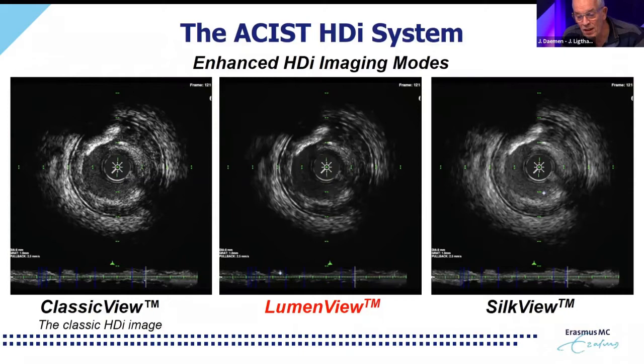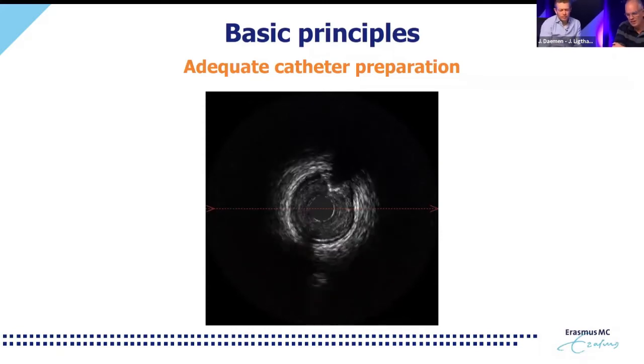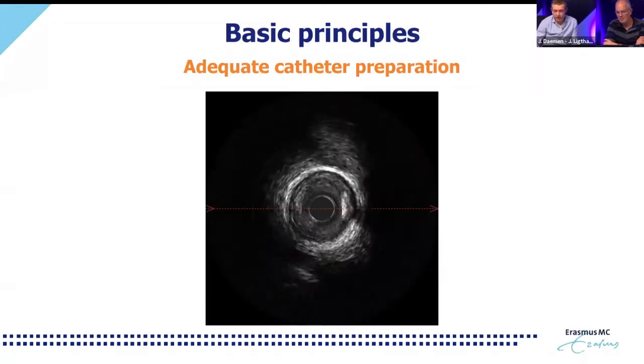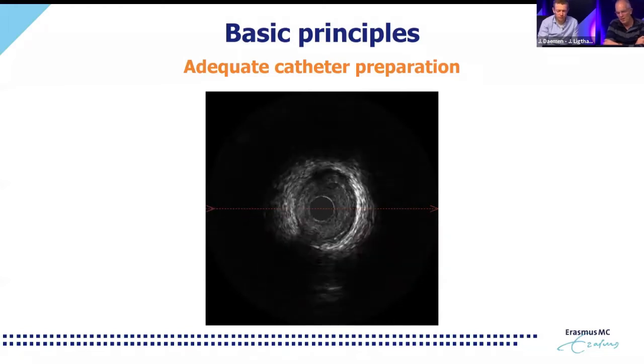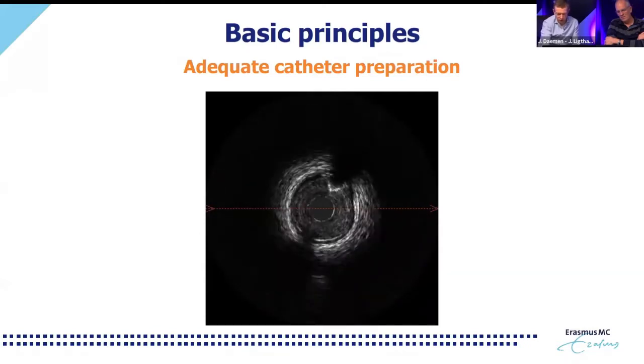Some basic principles when starting with IVUS — things that seem obvious but appear frequently as issues when we review cases. First: take the time to prepare the catheter well. This means adequately flushing the catheter according to the IFU — we typically do this in three steps over the rail. Make sure you do it properly, because otherwise you get images where, at the spot of interest, you lose the image due to air bubbles in the catheter lumen.